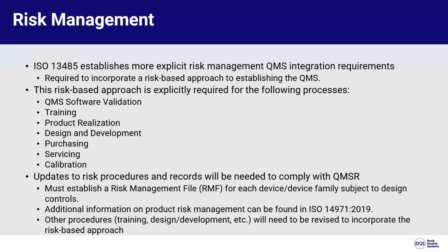This is based off of the ISO standard 14971, which is risk management for medical devices. Current revision is 2019. And one key thing for the integration of risk management into the design and development process is making sure that the outputs of risk management, so any risk controls or any newly identified risk, are captured within your design and development records as design inputs or outputs.